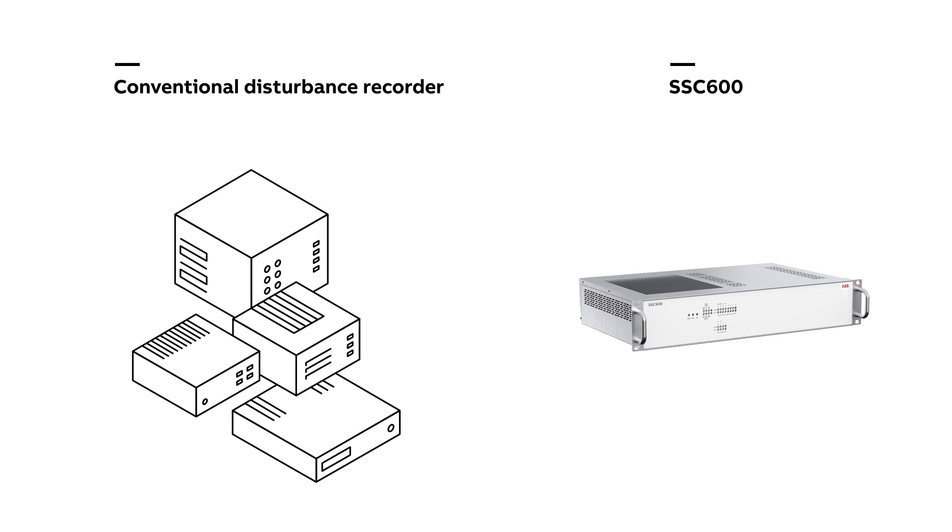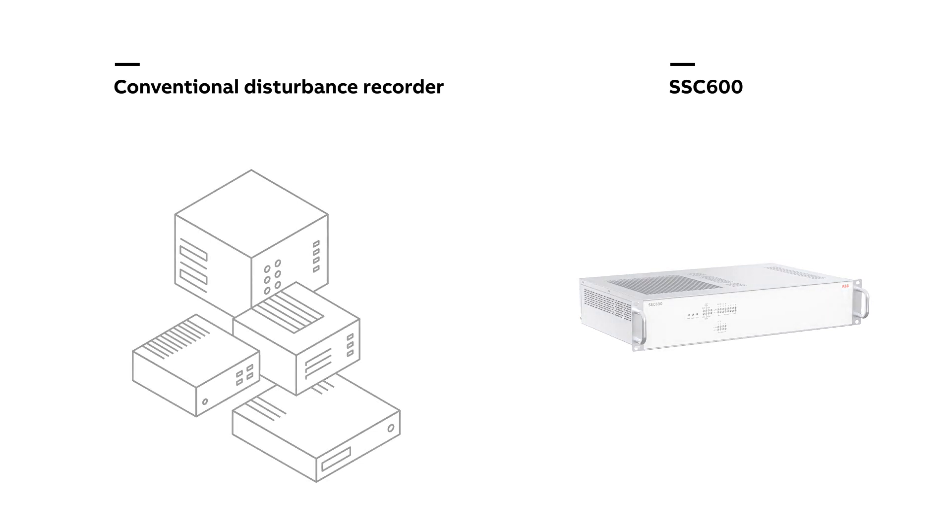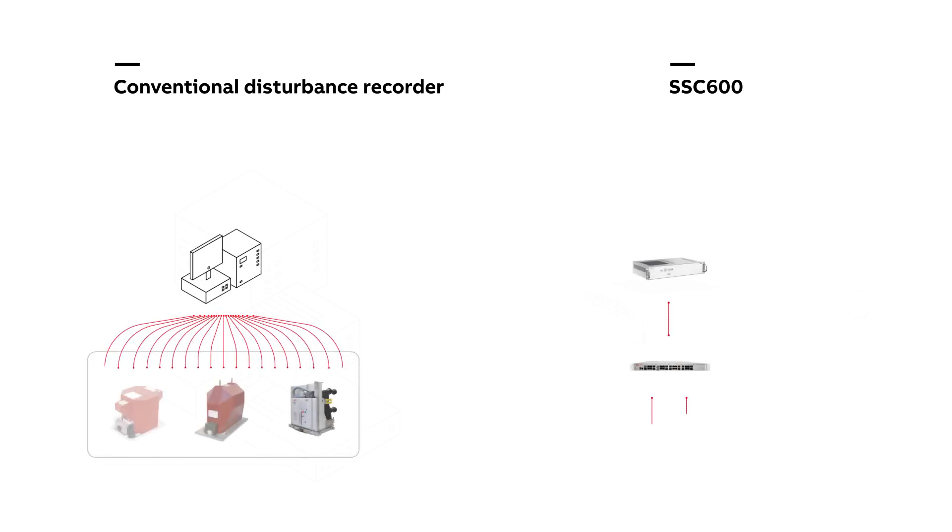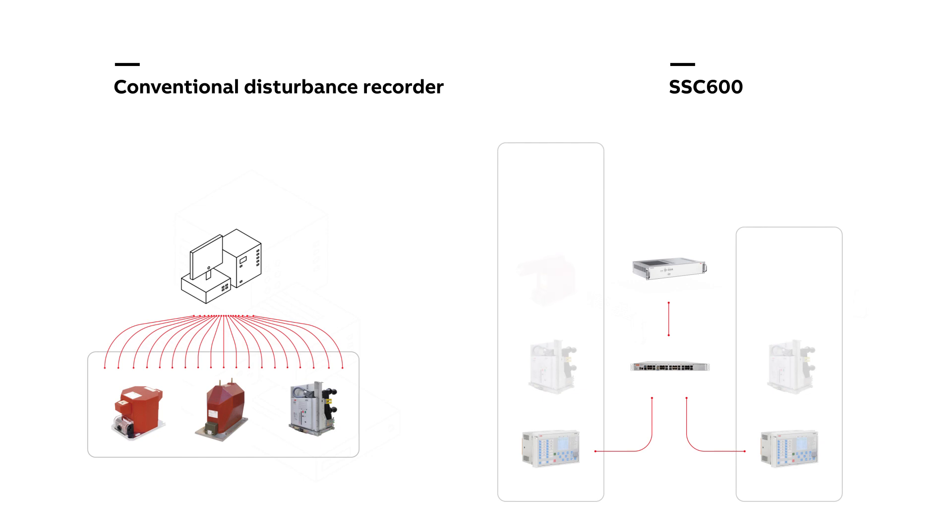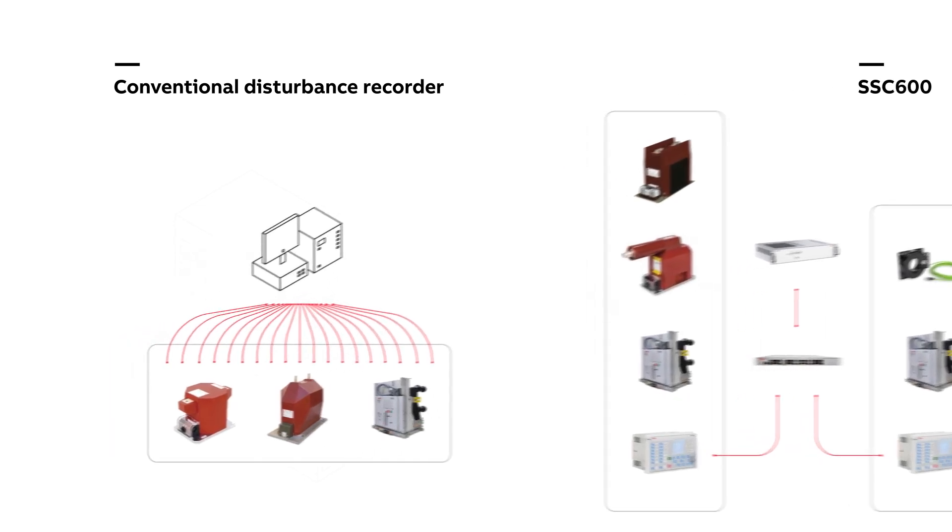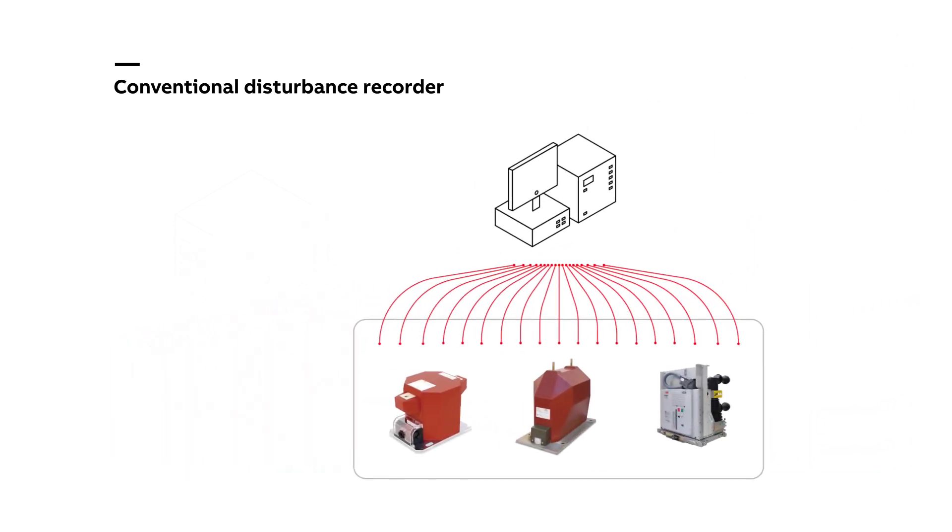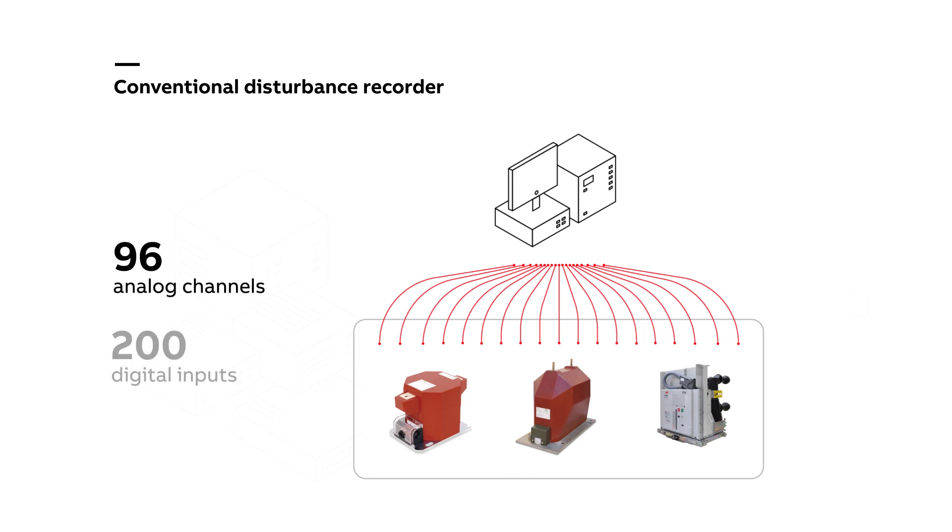Now let's move to look at examples comparing a conventional disturbance recorder to an SSC 600 application. Here is one example of a conventional disturbance recorder, and it has 96 analog channels and almost 200 digital inputs. It is receiving signals from conventional CTs, so in a three-phase system, three CTs means six wires per panel, six wires from VTs, and several wires from the circuit breaker, the protection relay, the lockout relay, and the emergency stopper button.